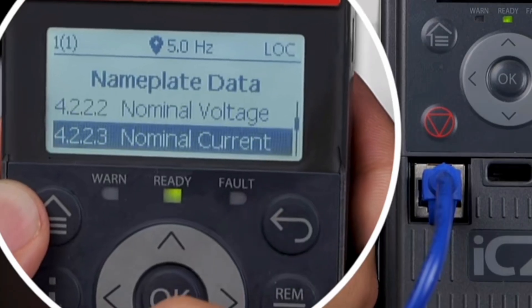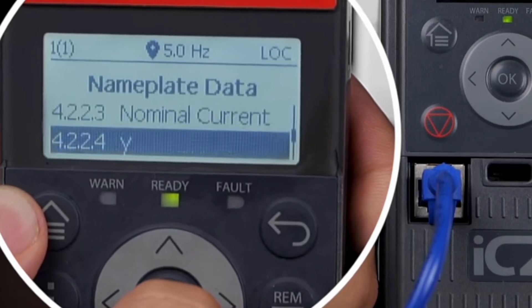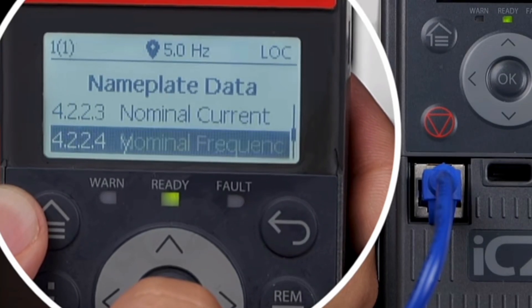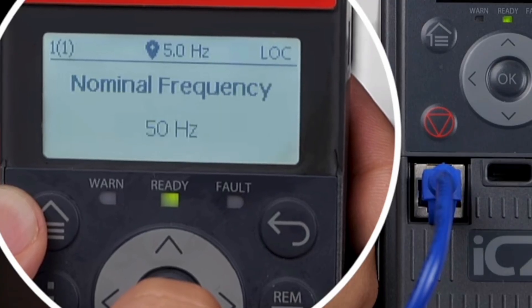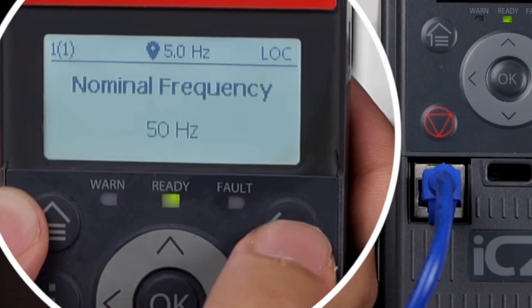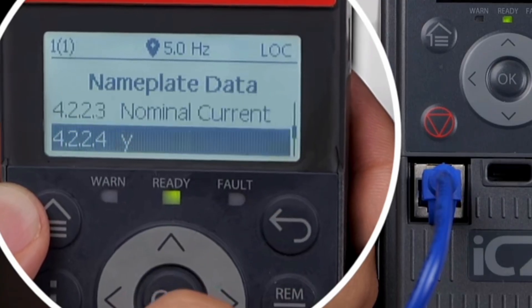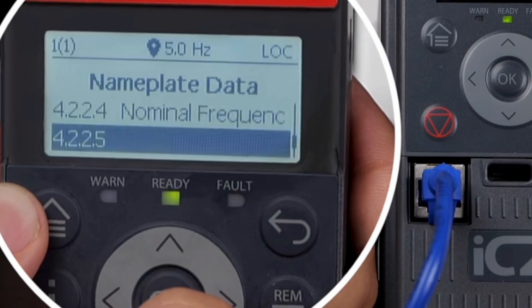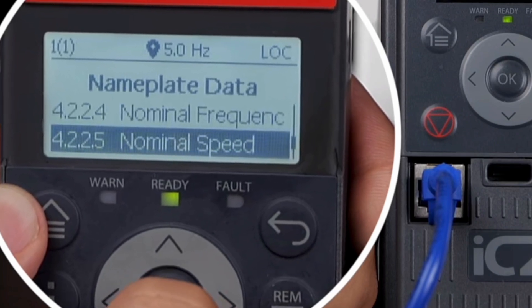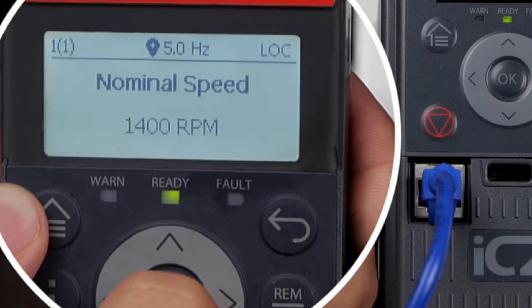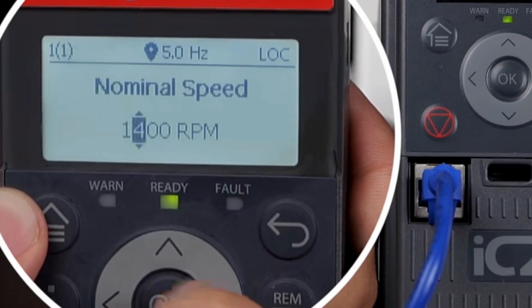Select parameter 4224 and set the nominal frequency to 50 hertz. Select parameter 4225 and set the nominal speed to 1440 RPM.